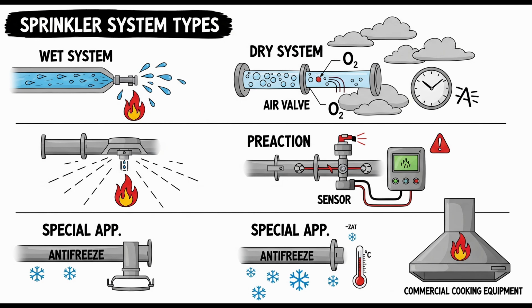Antifreeze solutions, just like water, expand significantly when they get warmer and contract when they get colder. Thermal expansion and contraction. Right. In a closed system, this thermal expansion can build dangerously high pressures, potentially damaging sprinklers or fittings. Contraction can create negative pressure or vacuum conditions. A listed expansion chamber acts as a buffer or accumulator. It contains a precharged air bubble, usually separated by a diaphragm or bladder, that compresses to absorb the expanding liquid volume when heated and expands to push liquid back out when cooled. Like a shock absorber specifically for temperature-induced volume changes.